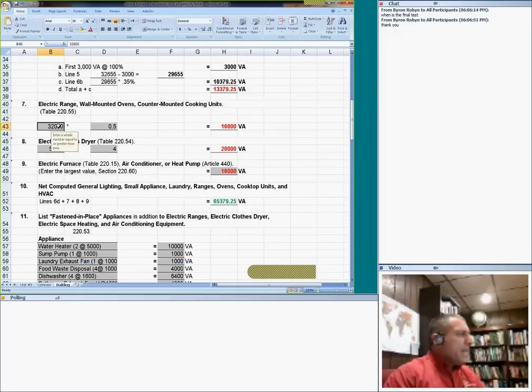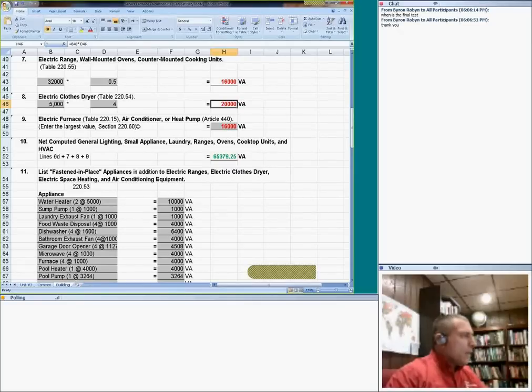Ranges. I have, for this project, guys, four apartments in one quadruplex. I have eight kW units, 8 times 4, 32. Then you take the 0.5 from table 220.55. That will get you a demand of 16. Can you guys see that? These are multiplied. And then for dryers, I have 4 dryers. 4 times 5 gives you this amount and no demand because 4.